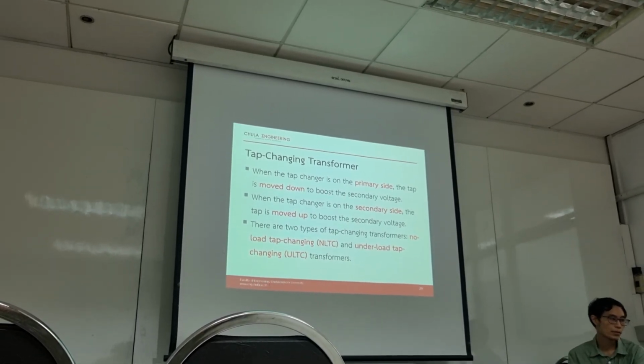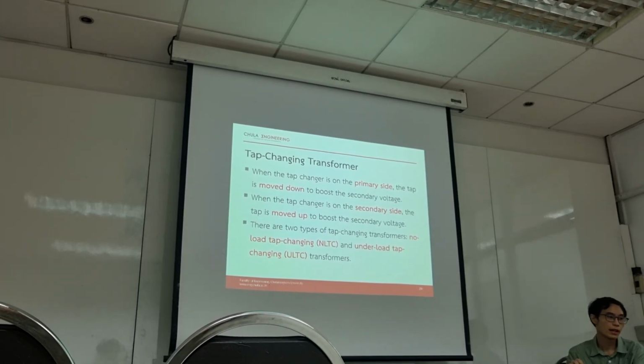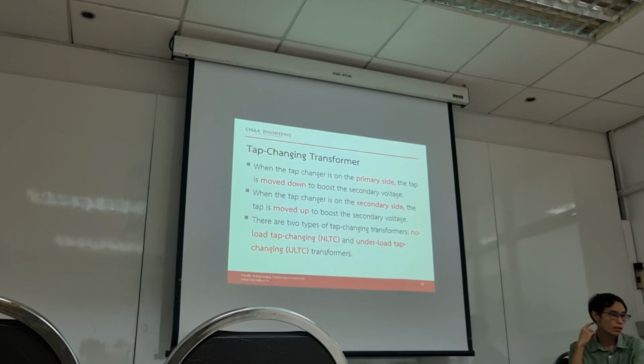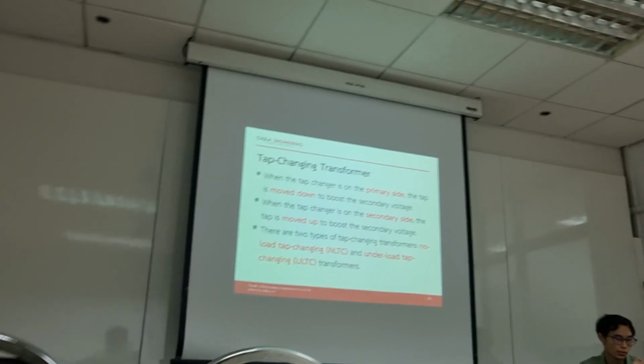If the tap is on the primary side, you can move the tap down to boost the secondary voltage. Or if the tap is on the secondary side, you can move the tap up to boost the voltage.